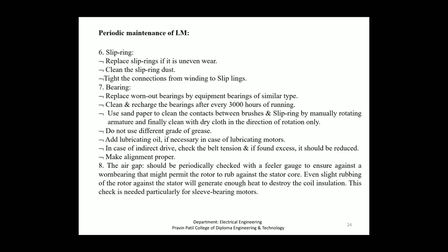Next, slip rings. Replace the slip ring if there is uneven wear. Then clean the slip ring dust. Next, tighten the connection from the winding to slip rings. Next is the bearing. Replace worn out bearings with equivalent bearings of similar type. Clean and recharge the bearings after every 3000 hours of running. Next, use sandpaper to clean the contact between brushes and slip ring by manually rotating the armature, and finally clean with a dry cloth in the direction of rotation only.